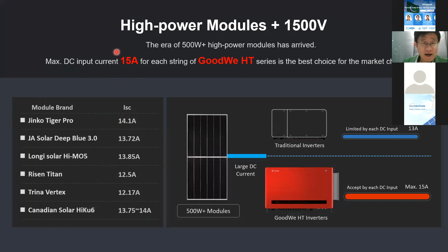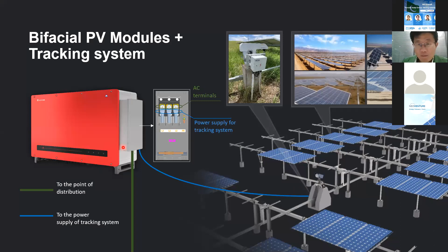Now I will tell you about our new technology. First, as Mr. Kim from Trina just mentioned, nowadays PV modules are increasing their ISC, the input current. Our new generation products can fully accept 15 amperes for each string, and our inverters can support bifacial PV modules plus tracking systems. Especially, our inverters support AC terminals, which can supply AC power directly to the tracking system, and our products can communicate with the tracking system so we can monitor and control it within our monitoring system.